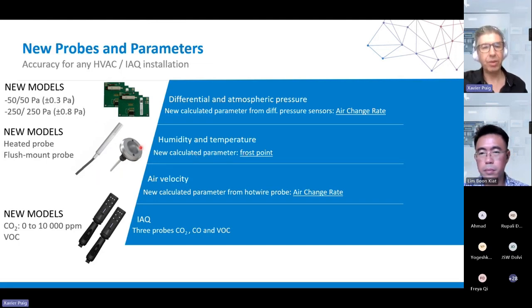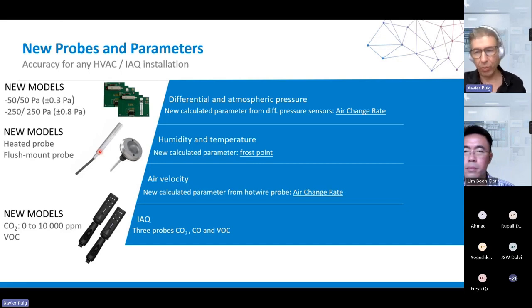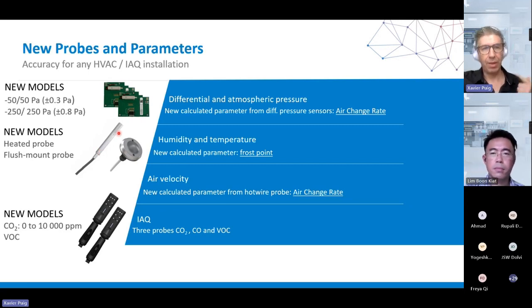When it comes to humidity and temperature, we have two new probes. The heated humidity probe, which is meant to be used in harsh environments where you have a high level of humidity in the air. So there's a risk of having drops on the sensor. When it's heated, like this one, that risk is eliminated. So there's no risk to damage the sensor regardless of the high humidity levels. So you can be perfectly between 95 and saturation, and the sensor is working perfectly fine. That's suitable for those applications: food industry, high demanding ventilation applications, for example, drying processes, and so on and so forth.